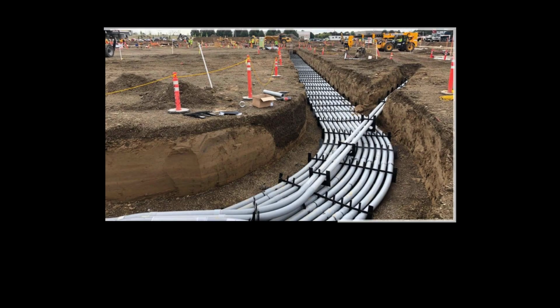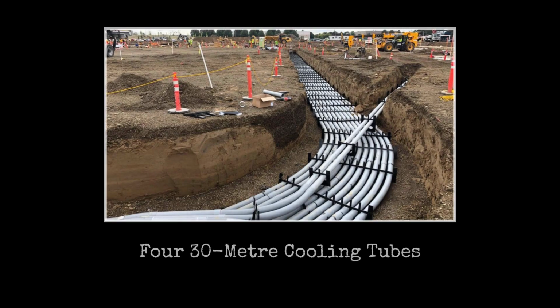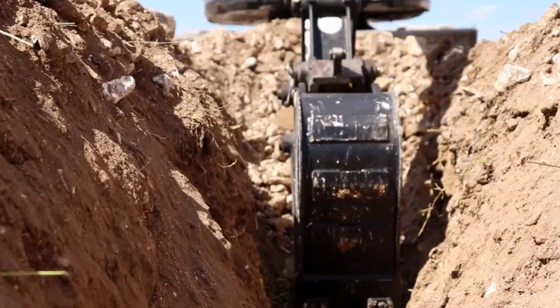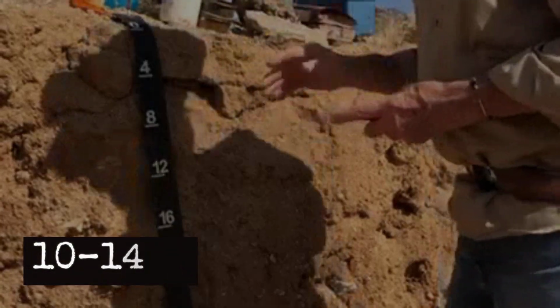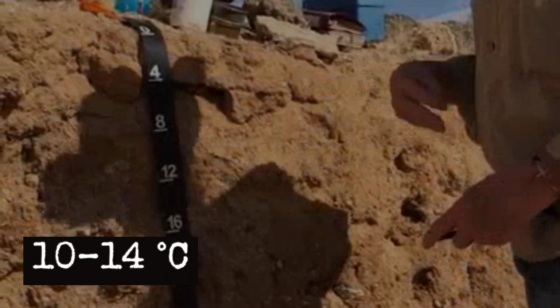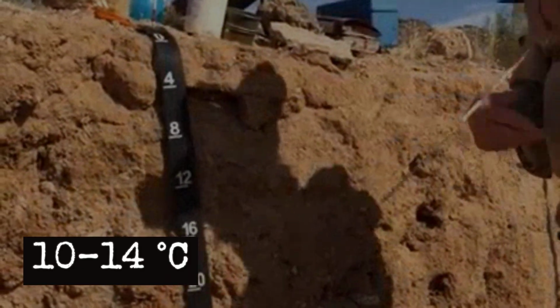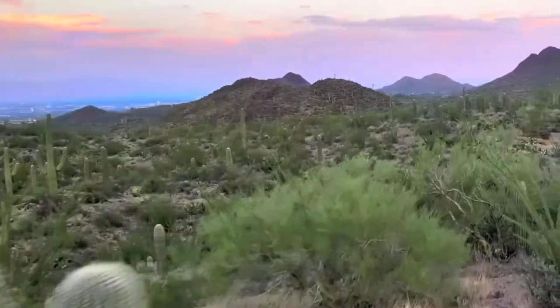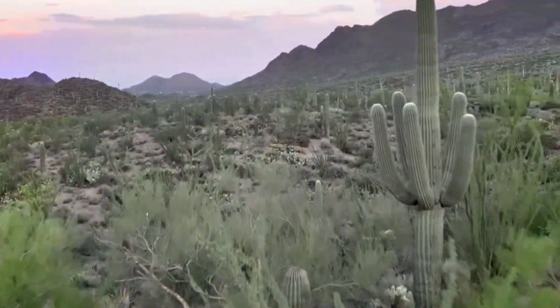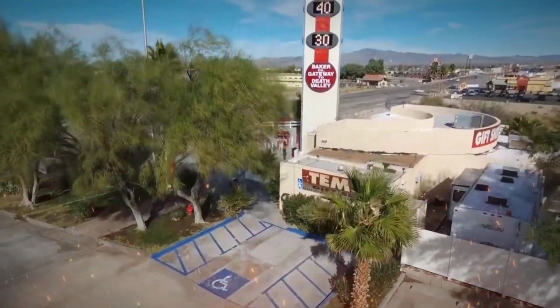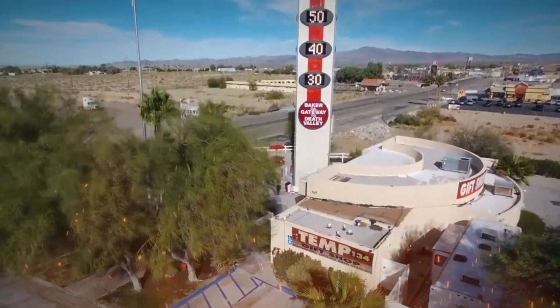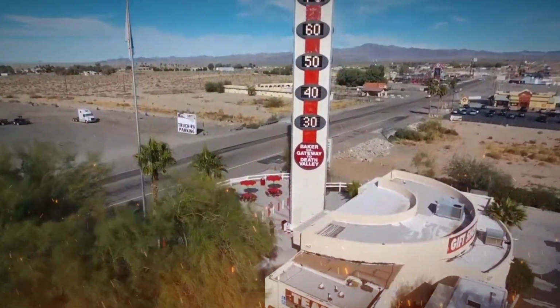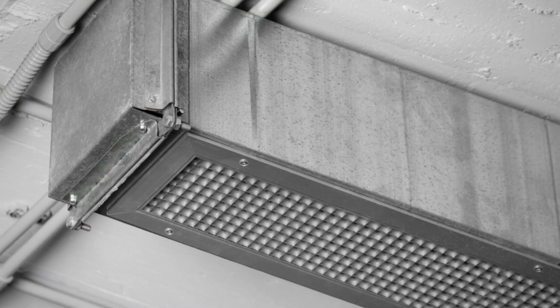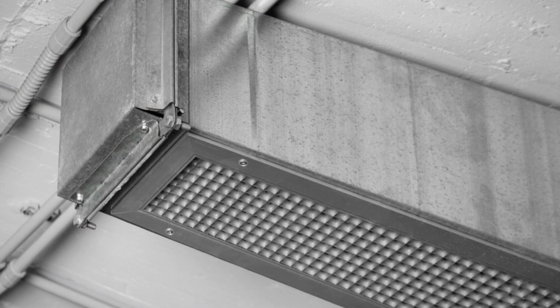4 parallel high-density polyethylene tubes, each 15 centimeters in diameter and 30 meters in length, were buried at a depth of 4 meters beneath the surface. At this depth, the soil temperature remains stable, hovering between 10 and 14 degrees Celsius year-round, regardless of the desert's surface extremes. During peak summer, as outdoor air climbed above 40 degrees Celsius, the system drew in fresh air and routed it through the buried tubes.